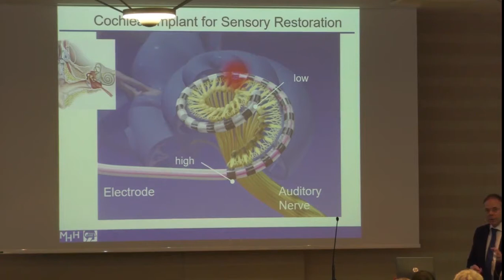The cochlear implant now rebuilds this type of frequency separation, and the high frequencies are presented by, for instance, this electrode contact, middle frequencies by this contact, and low frequencies by this contact. And doing so, you can activate different parts of the auditory nerve, as you can see here. So you see now the different frequencies are basically going to the different electrode contacts.